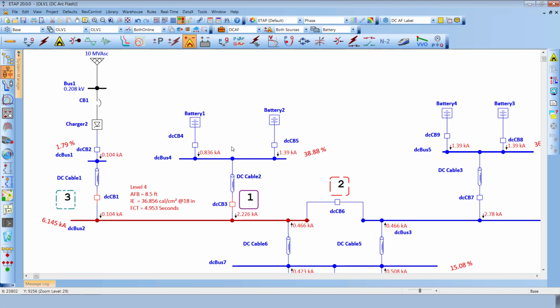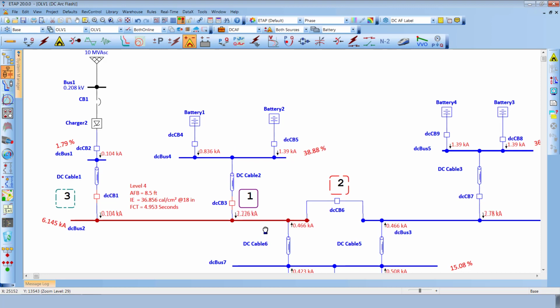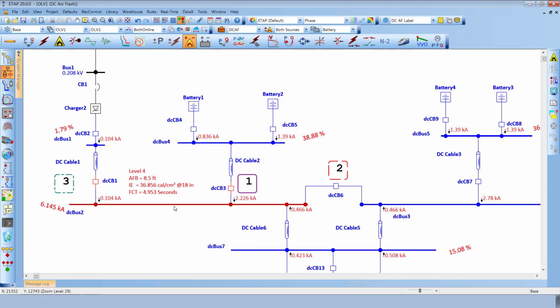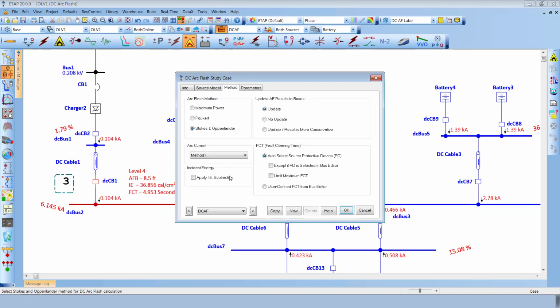For example, in this condition, ETAP can calculate the incident energy at DC bus 2, accounting for the removal of incident energy from each source after the corresponding protective device has de-energized the circuit. To enable this feature, the study case method tab is used. And I have created a new study case called DC arc flash underscore with subtraction, with the Apply Incident Energy Subtraction option selected.